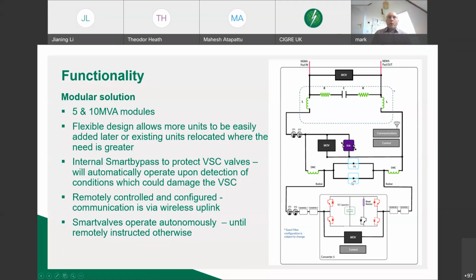One of the key points to mention is that these devices are all about protecting power electronics. There is no transformer coupling these to the system. The power electronics is directly in circuit. So the protection in here is all about making sure that the power electronics units themselves are not damaged under onerous fault duty conditions. That is a slight difference from some of the traditional assets used for power flow control, like quadrature boosters or series reactors, which sit there during the fault and have to take the full whack of fault current or overvoltages. Here, this bypass arrangement protects the device during anything that is beyond the rating of the power electronic capability.